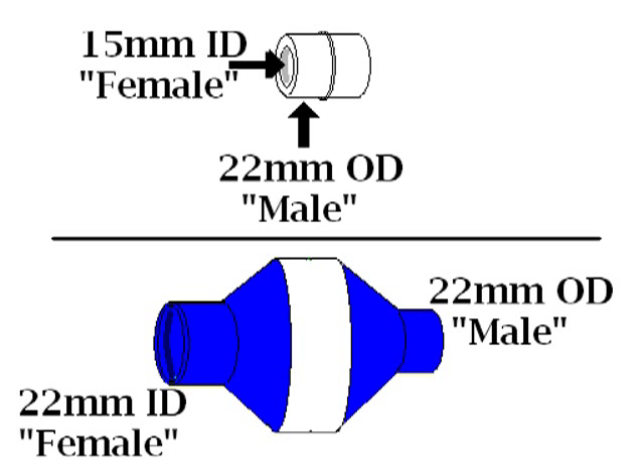There are also some transitional and multi-use pieces, such as a common adapter that has both a 22 millimeter OD on the outer edge so it can connect to blue tubing, but on the inside has a 15 millimeter female so it can connect directly to airways or HMEs. One end of a filter has a 22 ID female and the other end has a 22 OD male. If this were an HME, the 22 millimeter OD end might have a 15 millimeter airway attachment on the inside.